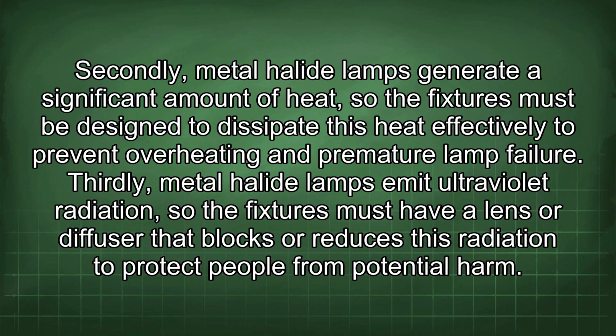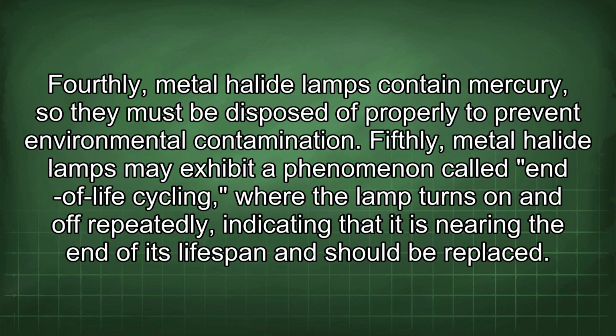Thirdly, metal halide lamps emit ultraviolet radiation, so the fixtures must have a lens or diffuser that blocks or reduces this radiation to protect people from potential harm. Fourthly, metal halide lamps contain mercury, so they must be disposed of properly to prevent environmental contamination. Fifthly, metal halide lamps may exhibit a phenomenon called end-of-life cycling, where the lamp turns on and off repeatedly, indicating that it is nearing the end of its lifespan and should be replaced.